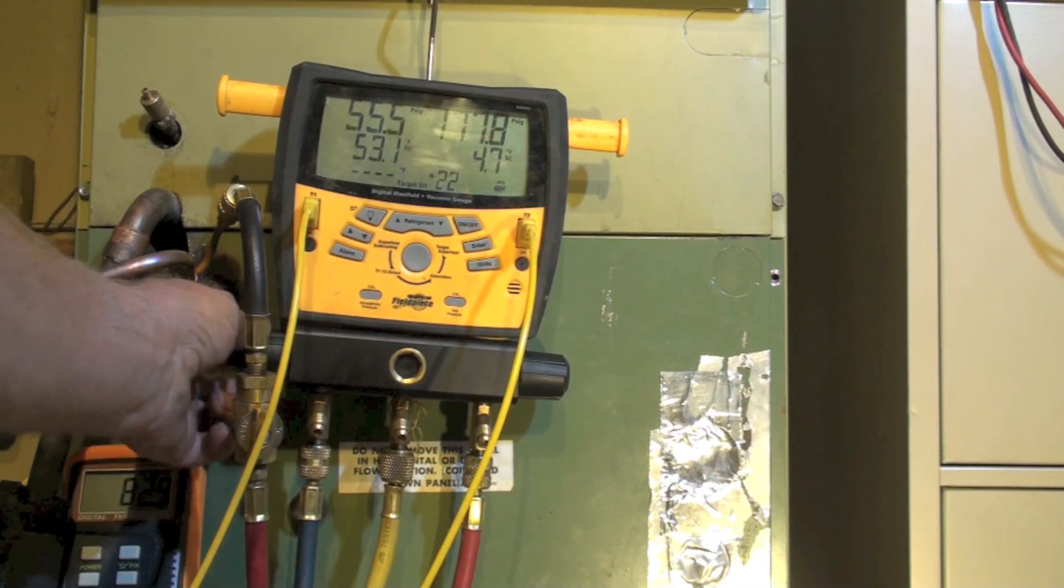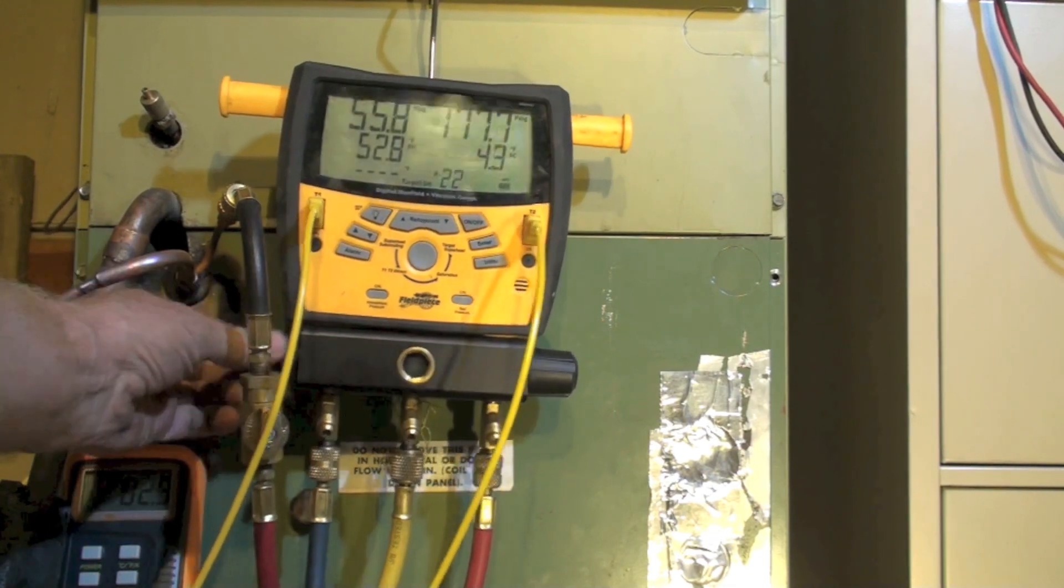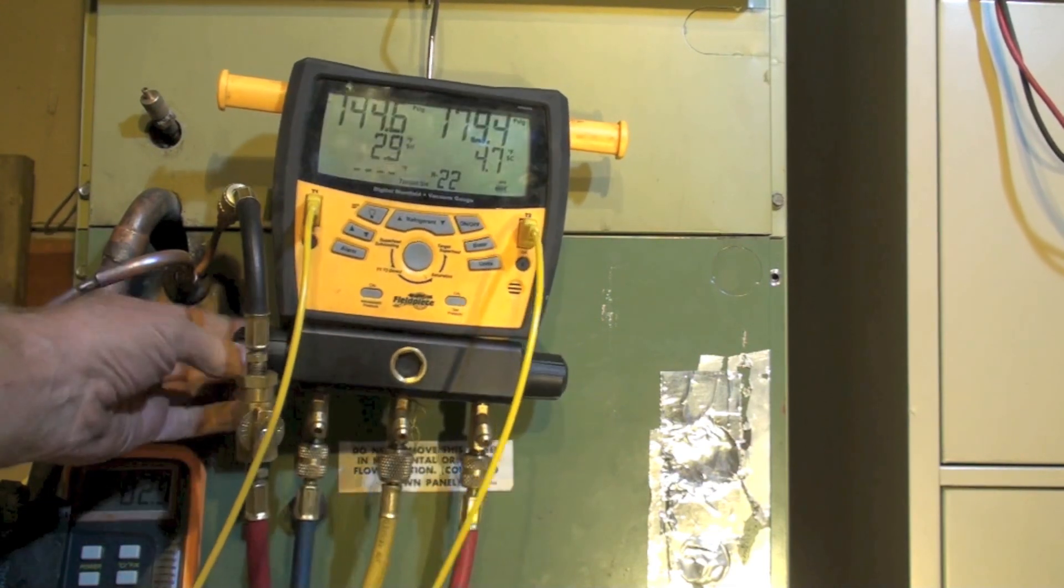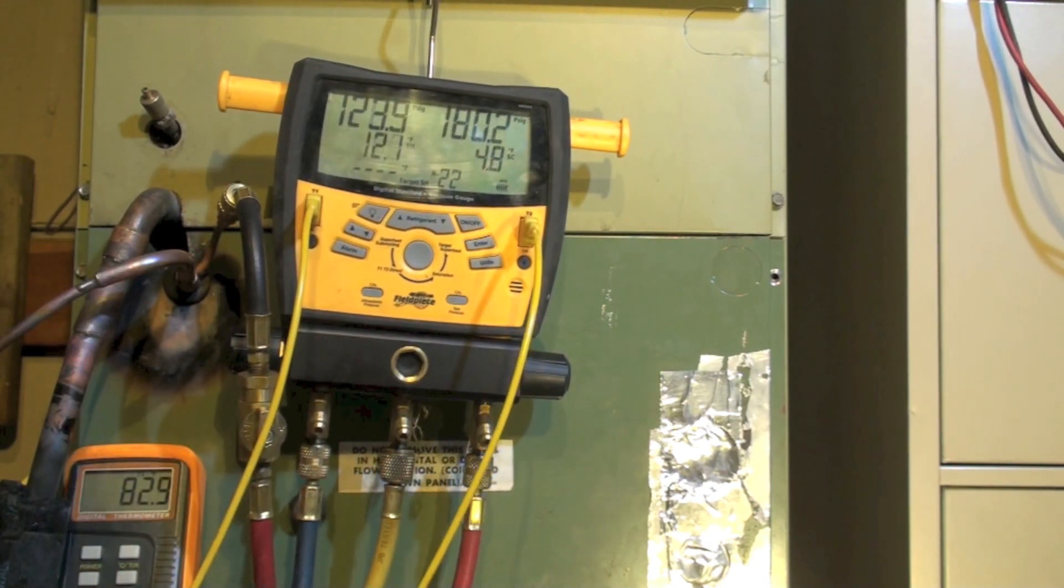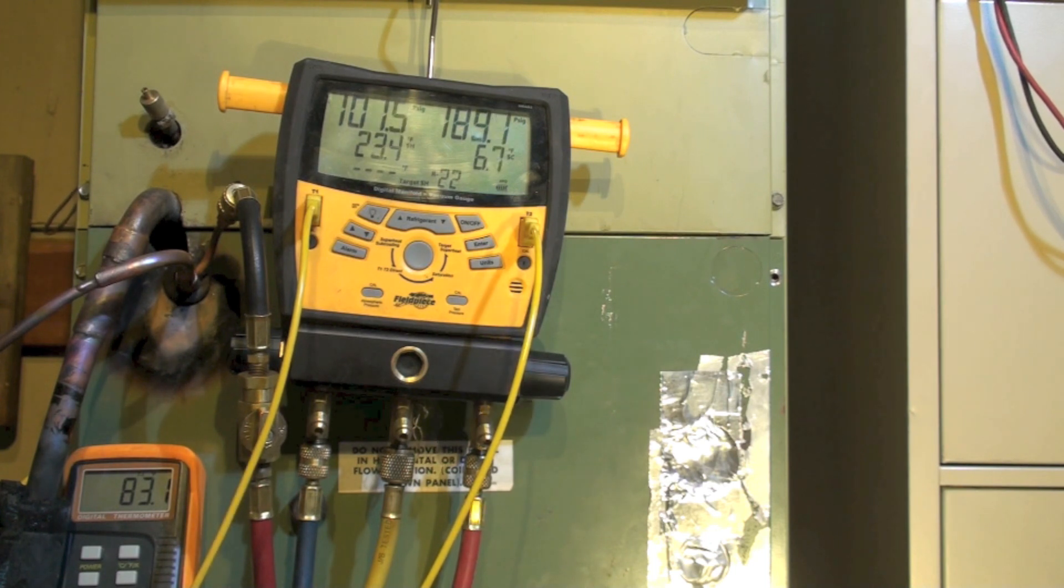Okay, we're adding refrigerant from the low side. I can turn this valve wide open. Listen close, you can hear the compressor load a little bit. Now the low side gauge is not going to make any sense because it's reading somewhere between the refrigerant cylinder pressure and the suction, and we'll have to shut it off every once in a while.